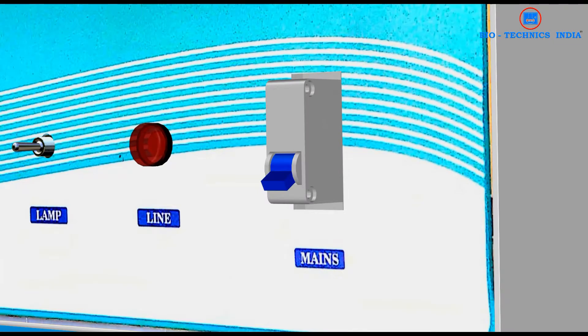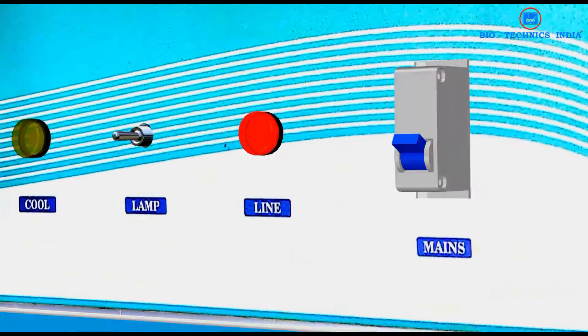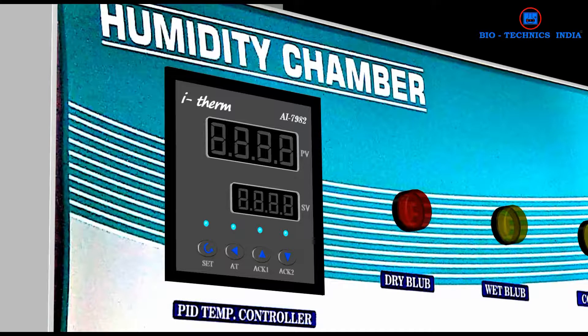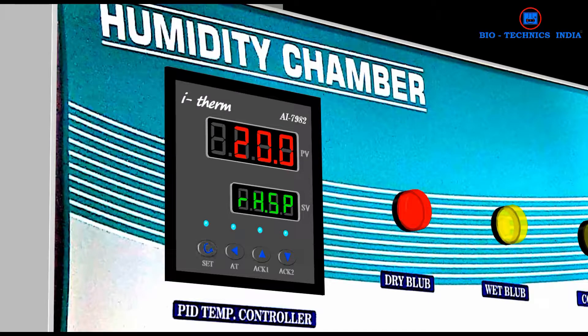To start the machine, switch on the mains, press the set key to indicate current temperature. Set the required temperature by using up and down key. Again press the set key to indicate relative humidity. Set the relative humidity by using up and down key. Press the set key to start the operation.